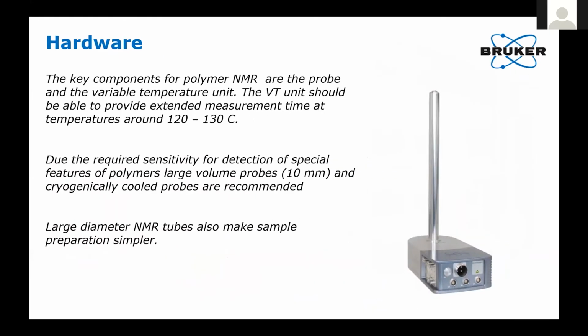The next aspect is the probe, and we heard Don earlier asking for input about the probes. We know that a key component for polymer NMR is variable temperature. So you want to go up to typically 120, 130 degrees. That's where a lot of the solvents are close to their boiling points. There are also dedicated high temperature probes, which can go up to 400 degrees C, where you can work with polymer melts. And that is definitely an interesting approach for these types of material.